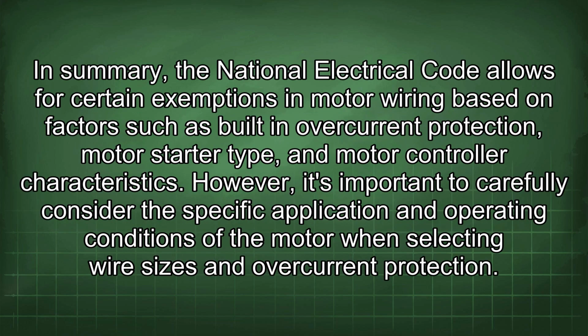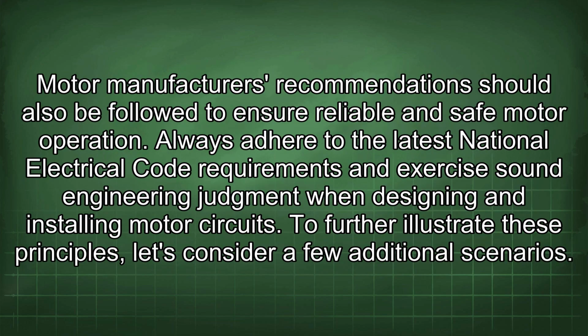In summary, the National Electrical Code allows for certain exemptions in motor wiring based on factors such as built-in overcurrent protection, motor starter type, and motor controller characteristics. However, it's important to carefully consider the specific application and operating conditions of the motor when selecting wire sizes and overcurrent protection. Motor manufacturers' recommendations should also be followed to ensure reliable and safe motor operation. Always adhere to the latest National Electrical Code requirements and exercise sound engineering judgment when designing and installing motor circuits.